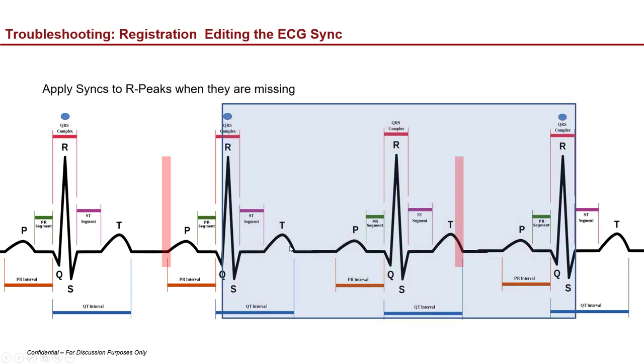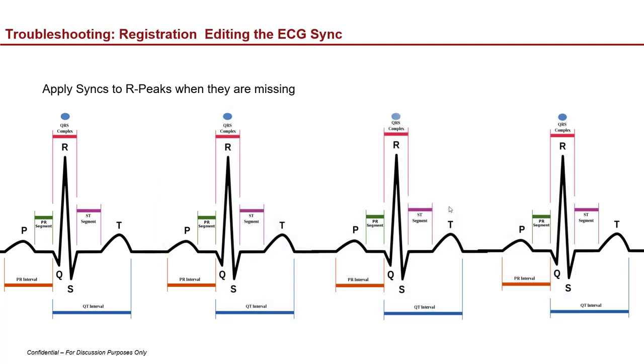What if you're missing a sync? If the system doesn't see an R peak and you've programmed it to give you 70% of the R-to-R cycle, it'll look at 70% between two detected R peaks — potentially merging diastole and systole together, which won't match. You'll want to make sure you add a sync to every R peak.